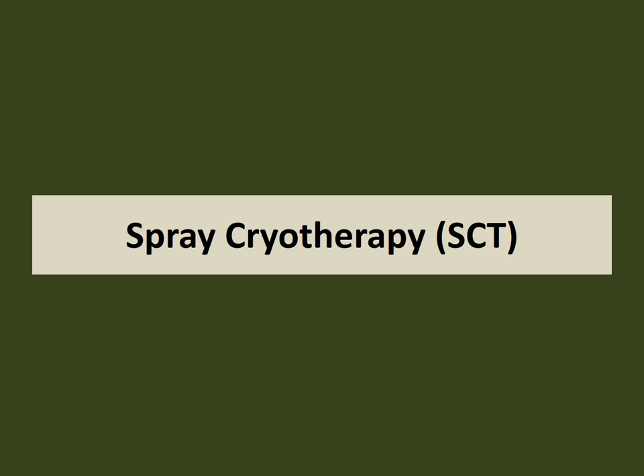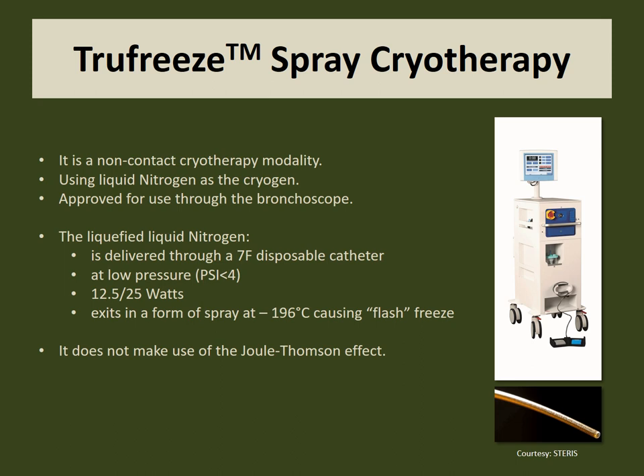Now let's review spray cryotherapy. A couple of devices are available commercially for the endoscopic application of cryospray. We will only discuss the Trufreeze spray cryotherapy system, which is becoming widely used for endoscopic application. It is a non-contact modality that delivers liquid nitrogen and is used to treat benign stenosis and airway tumors. Most of the data come from the GI literature in treating Barrett's and esophageal cancer, but the published literature on spray cryotherapy in the airways is growing. It delivers extremely cold liquid nitrogen spray at low pressure through a specialized small catheter, exiting at minus 196 degrees Celsius and causing flash freezing. This modality does not use the Joule-Thompson effect.